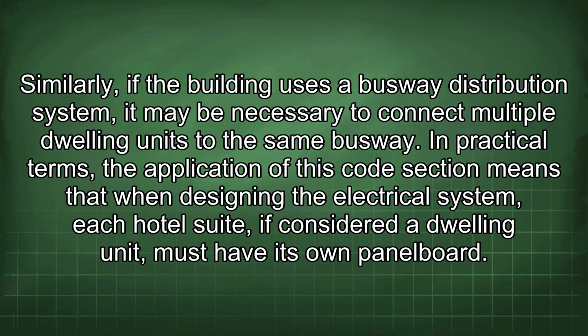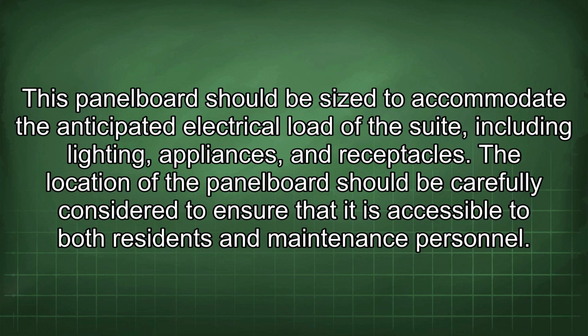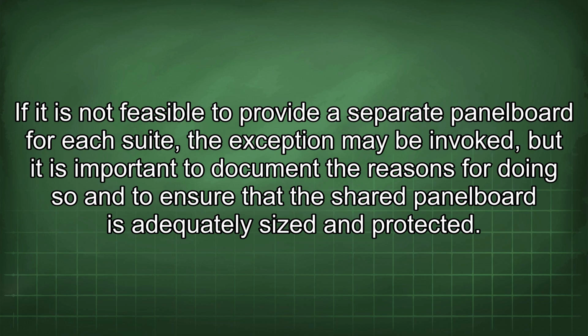Similarly, if the building uses a busway distribution system, it may be necessary to connect multiple dwelling units to the same busway. In practical terms, the application of this code section means that when designing the electrical system, each hotel suite, if considered a dwelling unit, must have its own panel board. This panel board should be sized to accommodate the anticipated electrical load of the suite, including lighting, appliances, and receptacles. The location of the panel board should be carefully considered to ensure that it is accessible to both residents and maintenance personnel. If it is not feasible to provide a separate panel board for each suite, the exception may be invoked, but it is important to document the reasons for doing so and to ensure that the shared panel board is adequately sized and protected.